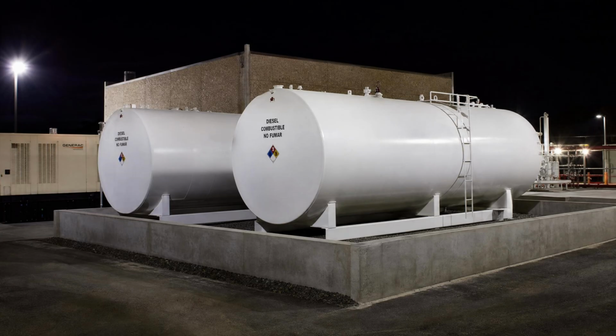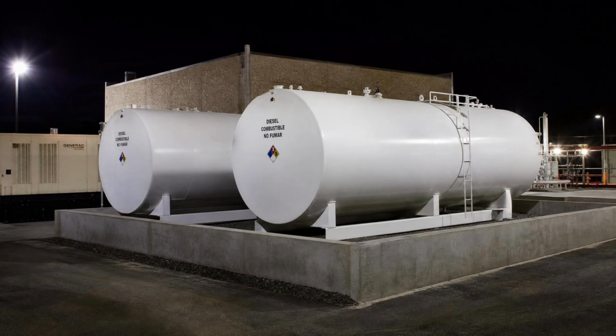The generator plant of a large hospital is a different scale of installation from what we imagined earlier in the commercial building. A large acute care hospital, the kind with hundreds of beds, multiple operating suites, an active emergency department, imaging equipment, and the full spectrum of clinical services, may have not one emergency generator but several. 2 or 3 or more large units arranged in a configuration that provides redundancy not just against utility failure but against the possibility of any single generator failing to start or failing during operation.